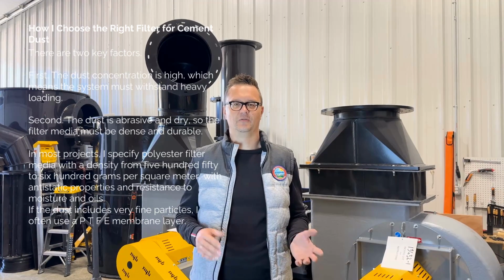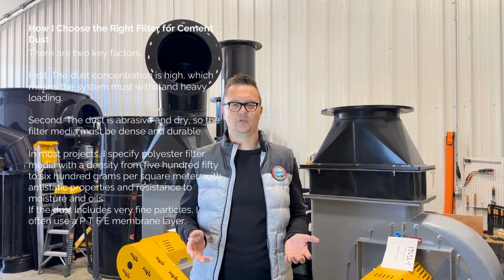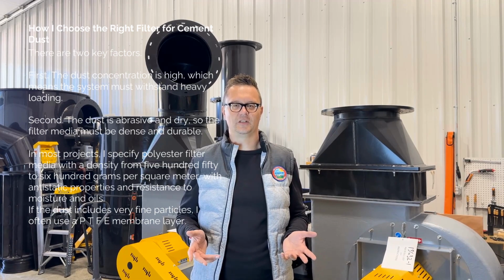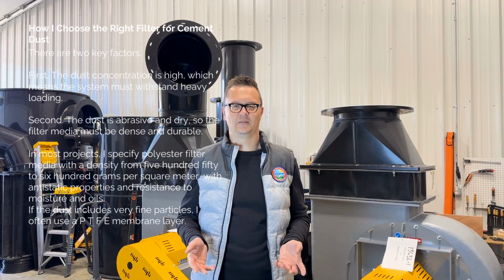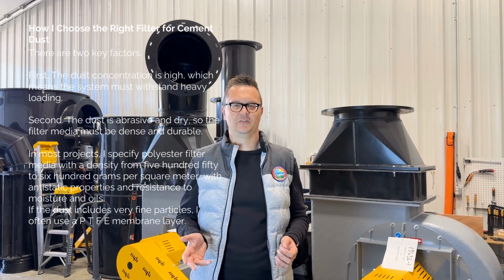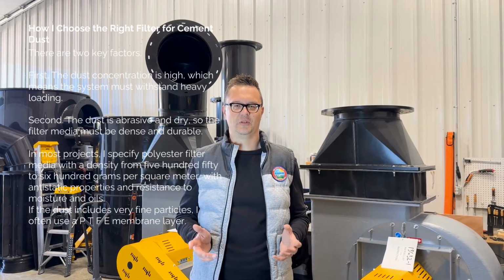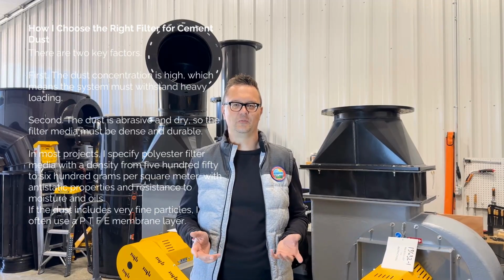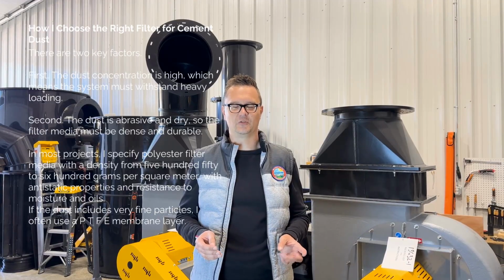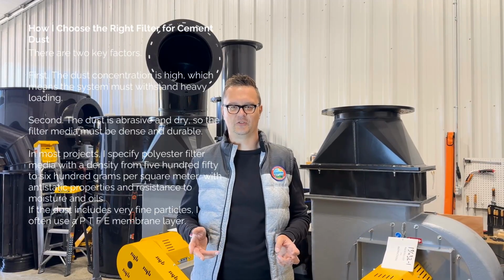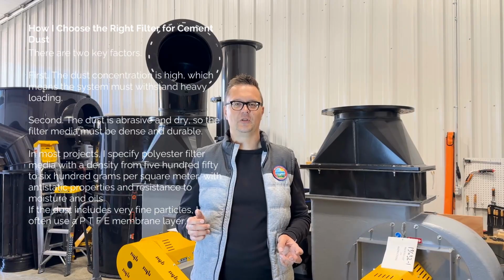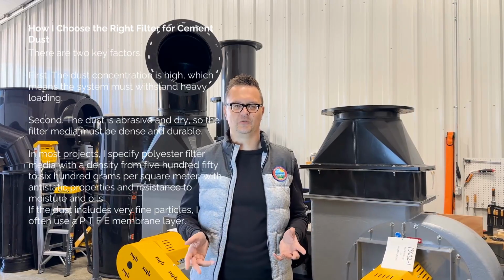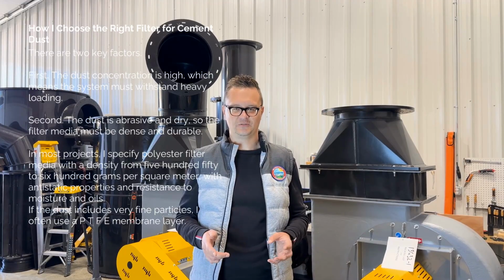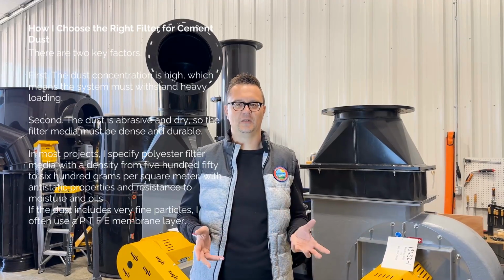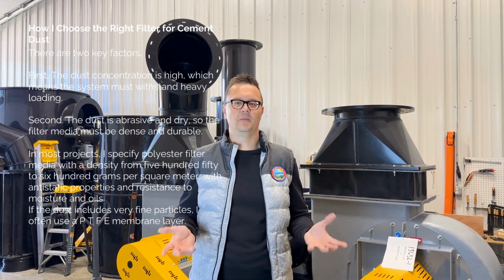How I choose the right filter for cement dust. There are two key factors. First, the dust concentration is high, which means the system must withstand heavy loading. Second, the dust is abrasive and dry, so the filter media must be dense and durable. In most projects, I specify polyester filter media with a density from 550 to 600 grams per square meter, with anti-static properties and resistance to moisture and oils. If the dust includes very fine particles, I often use a PTFE membrane layer.